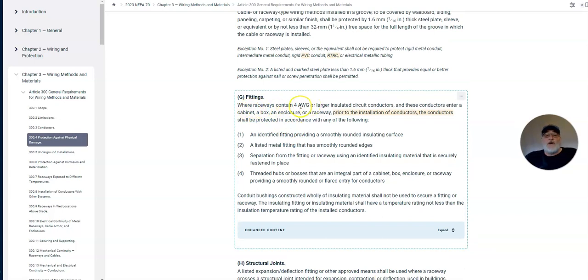Raceways where raceways contain number 4 AWG or larger insulated conductors, and these conductors enter a cabinet, a box, an enclosure, or raceway prior to the installation of the conductors, shall be protected in accordance with the following: an identified fitting providing a smoothly rounded insulated surface, a listed metal fitting that has smooth round edges, separation from the fitting of the raceway using identified insulation material that is securely fastened in place, or threaded hubs or bosses that are integral to part of a cabinet, enclosure, or raceway, providing a smooth, round, or flared entry for these conductors.